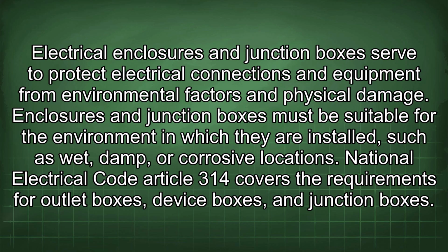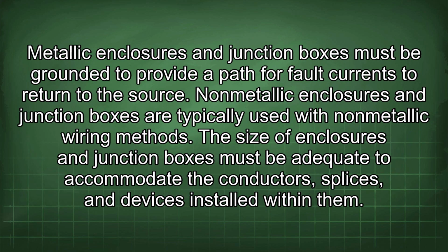damage. Enclosures and junction boxes must be suitable for the environment in which they are installed, such as wet, damp, or corrosive locations. National Electrical Code Article 314 covers the requirements for outlet boxes, device boxes, and junction boxes. Metallic enclosures and junction boxes must be grounded to provide a path for fault currents to return to the source. Non-metallic enclosures and junction boxes are typically used with non-metallic wiring methods. The size of enclosures and junction boxes must be adequate to accommodate the conductors, splices, and devices installed within them.